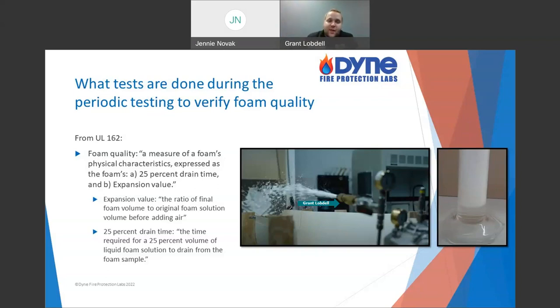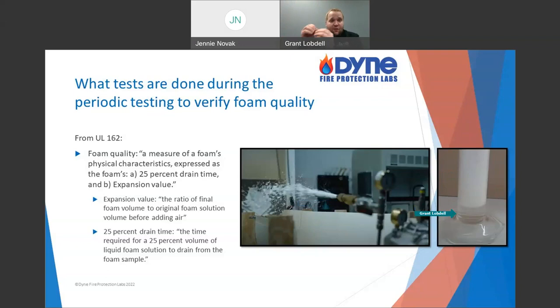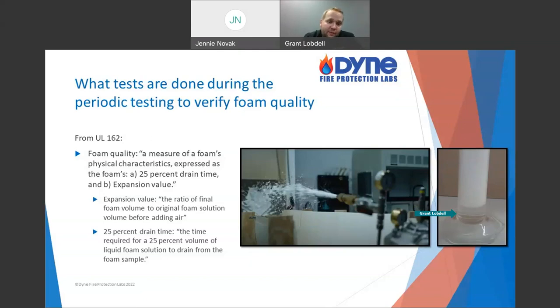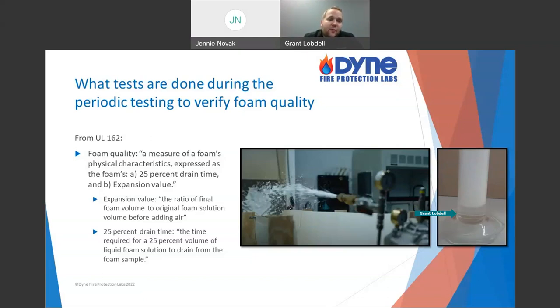That's what we're talking about when we discuss drainage time. You can see the foam blanket on top in the picture here. As the bubbles start to dissolve and pop, the solution itself isn't disappearing — I've just taken my solution and expanded it with air. As that water drains and the solution goes back down, we measure how long it takes. In this case, 25% drain time is a common benchmark for low expansion foam — how long does it take for 25% of that solution to return from foam back to liquid form?